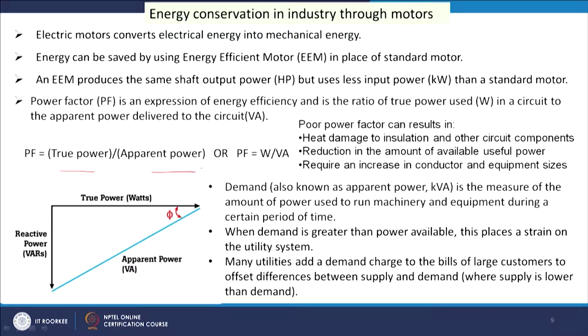Now, energy conservation in industry through motors. When motors are used in industry, we must be careful about their operation, because in some cases the power coming to the motor is not completely converted to useful work. This is due to the power factor, which equals true power divided by apparent power, that is, W by VA. Power factor is an expression of energy efficiency and is the ratio of the true power in a circuit to the apparent power delivered to the circuit.